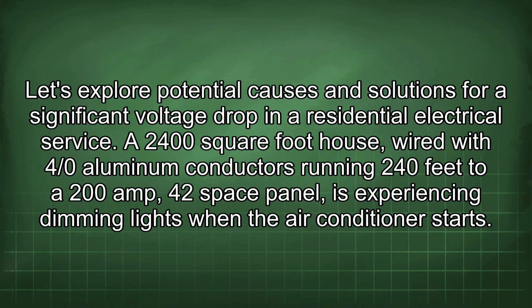Let's explore potential causes and solutions for a significant voltage drop in a residential electrical service. A 2,400 square foot house, wired with 4/0 aluminum conductors running 240 feet to a 200 amp 42 space panel, is experiencing dimming lights when the air conditioner starts.